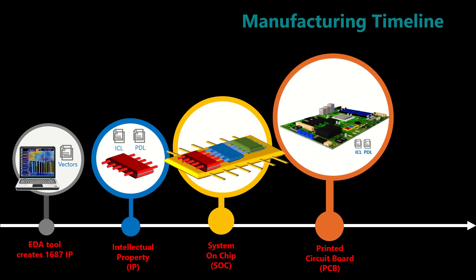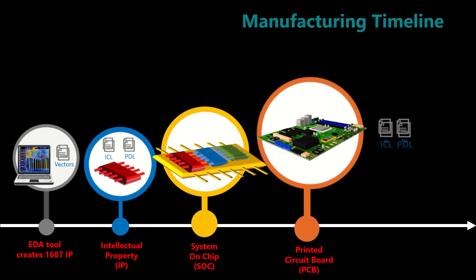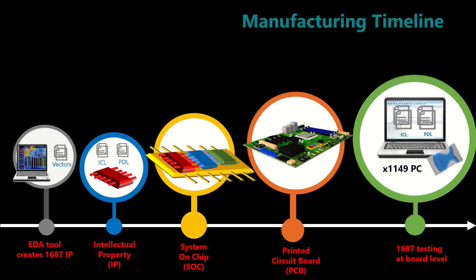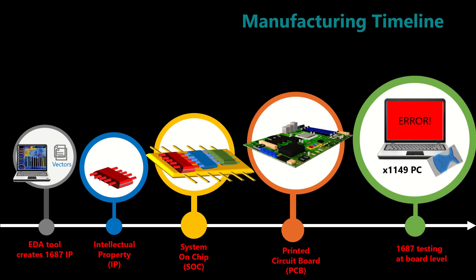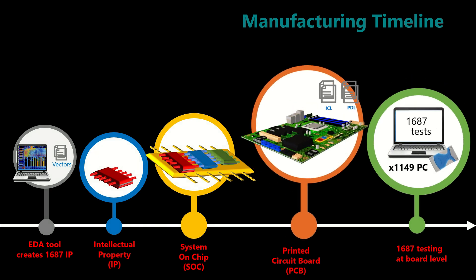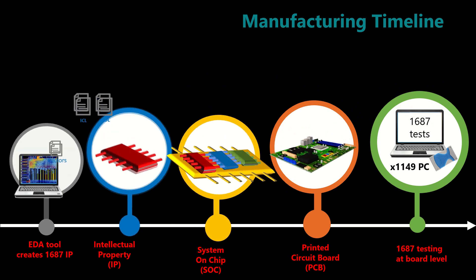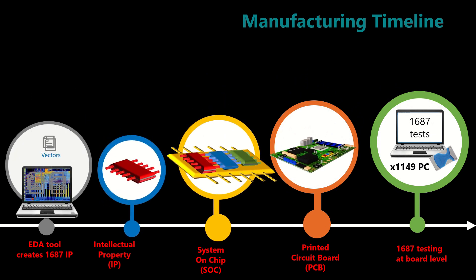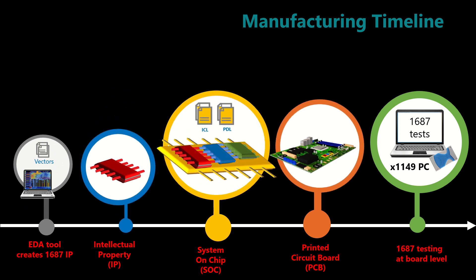While running the boundary scan test on the board, we run 1687 tests as well on devices that support 1687. If there are any defects in the IP blocks of the chip that are not detected, it could become a potential escape to manifest into functional test, which may impact functional test yield. With the help of 1687 test, it can help to minimise NTF issues by identifying more causes of failure. It also enables early-life failure detection of the silicon, tracing back to the manufacturing site to modify the ICL and PDL files, allowing failures to be easily correlated and reproduced at different stages of test.